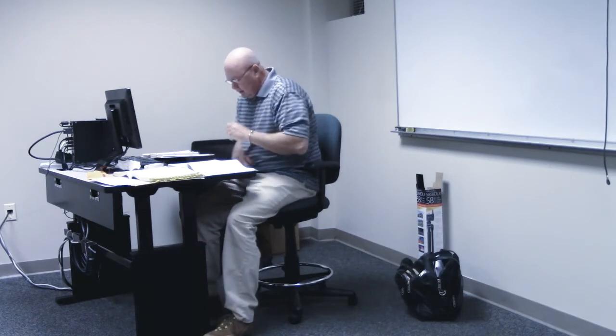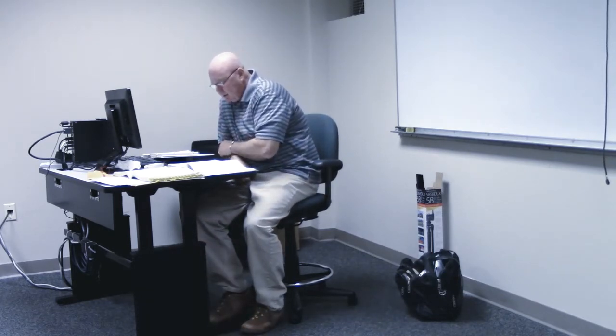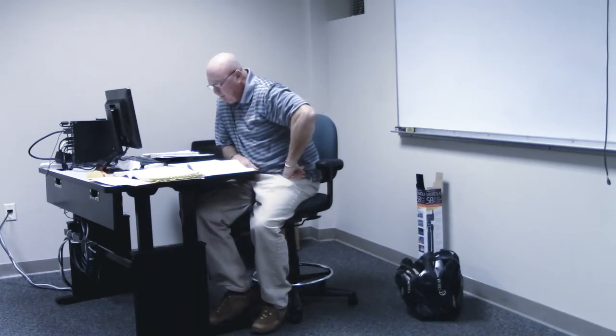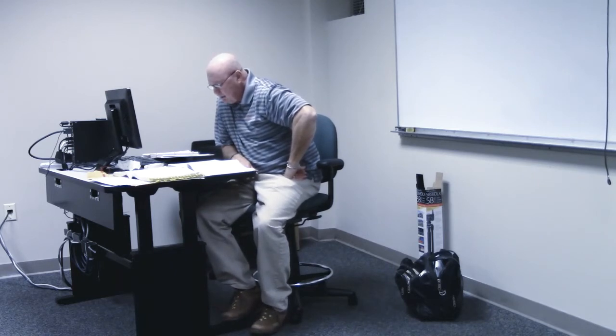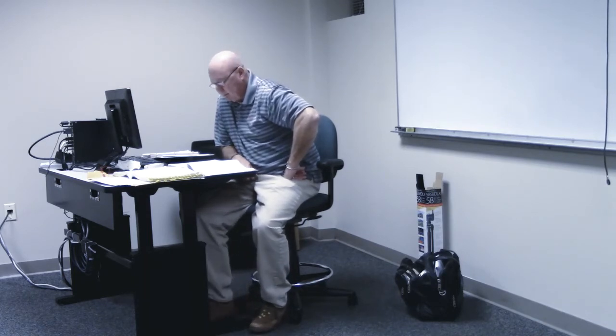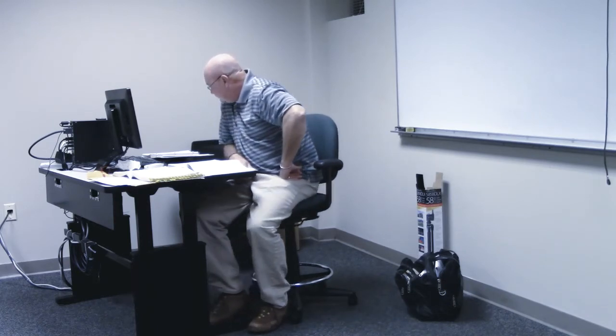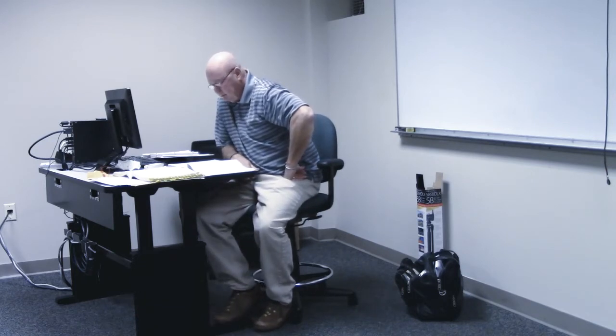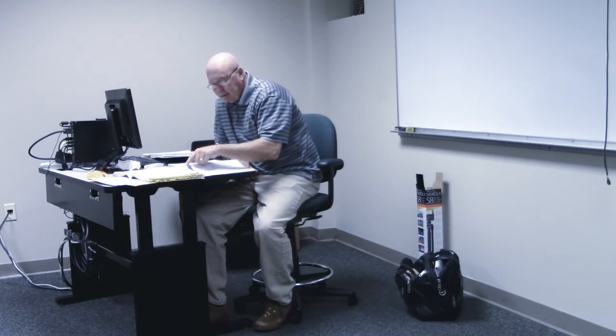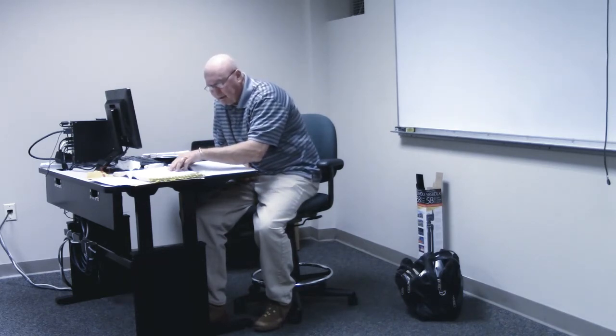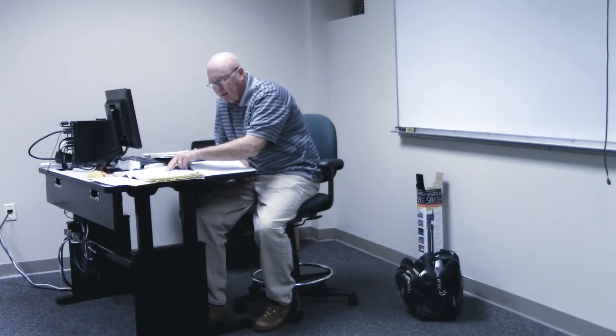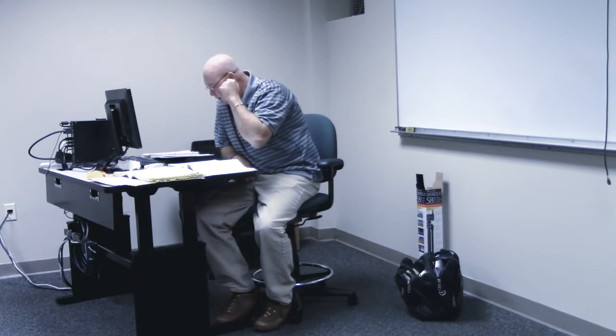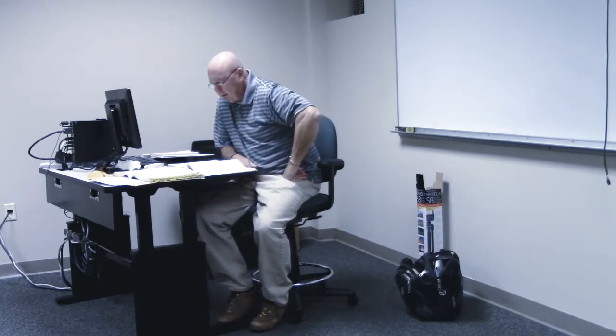The other thing that I want you to know, at the top of page 21, you see that sentence: individual branch circuits are not required for portable, mobile, and transportable medical X-ray equipment requiring a capacity of no more than 60 amps. I know that. No more than 60 amps. I highlight that. You might see that again. And that's per NEC 517.71(B), and we see it listed there if you look at your code. So again, that would be a smaller unit. That tells you most of your units are probably larger than that. Most of them are typically about 100 amp loads.